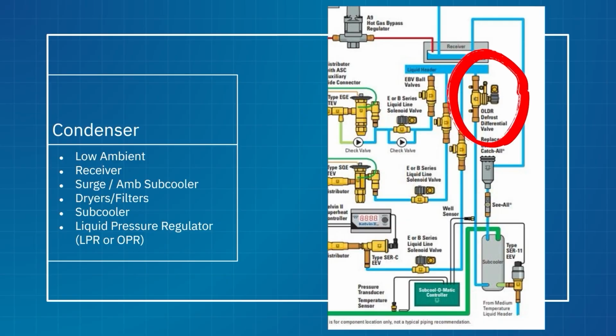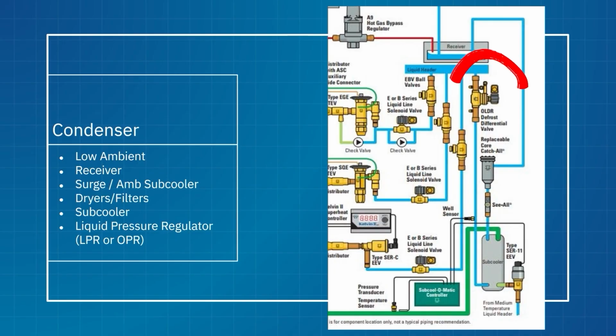So this version, what they've got drawn in here is an OLDR valve, okay? That is for hot gas defrost. That particular valve is for hot gas defrost. I just said I was gonna talk about that, right? But hold on, there's a function of this valve, and this valve, my liquid coming out of here and going towards my liquid header that's gonna feed my cases.